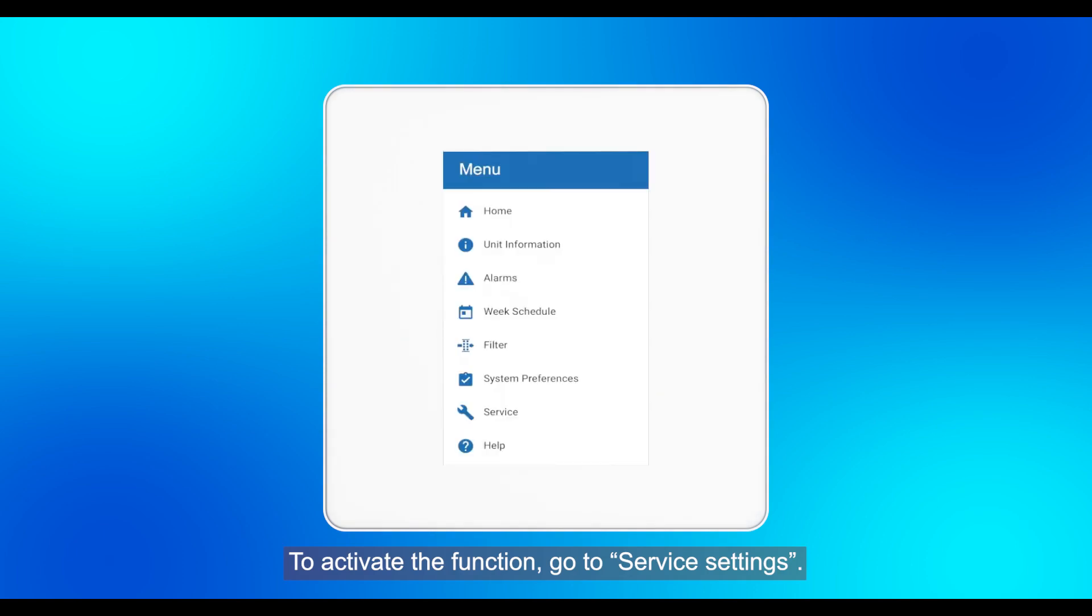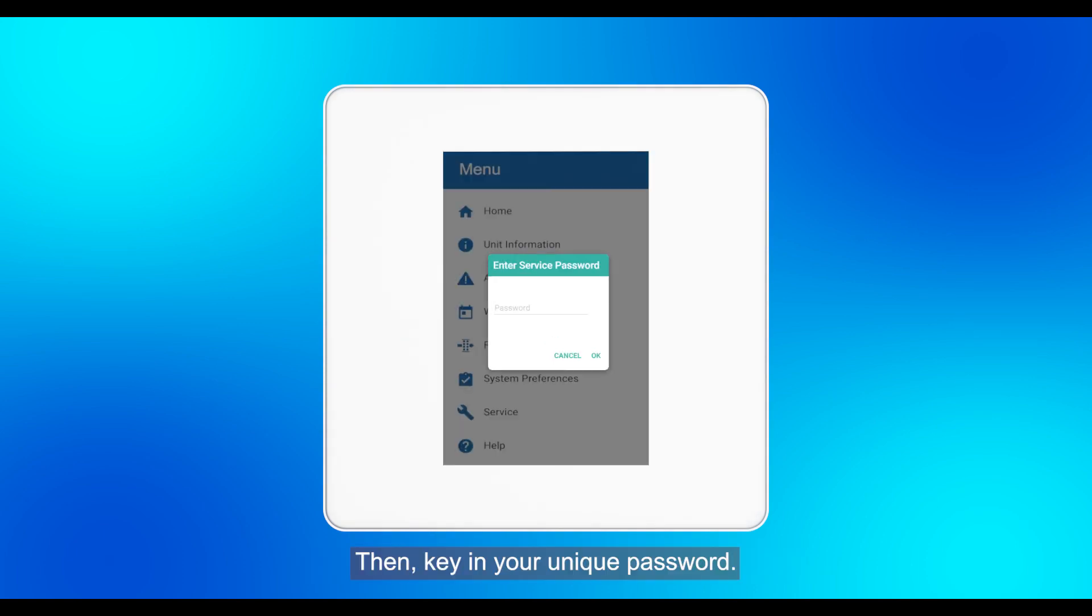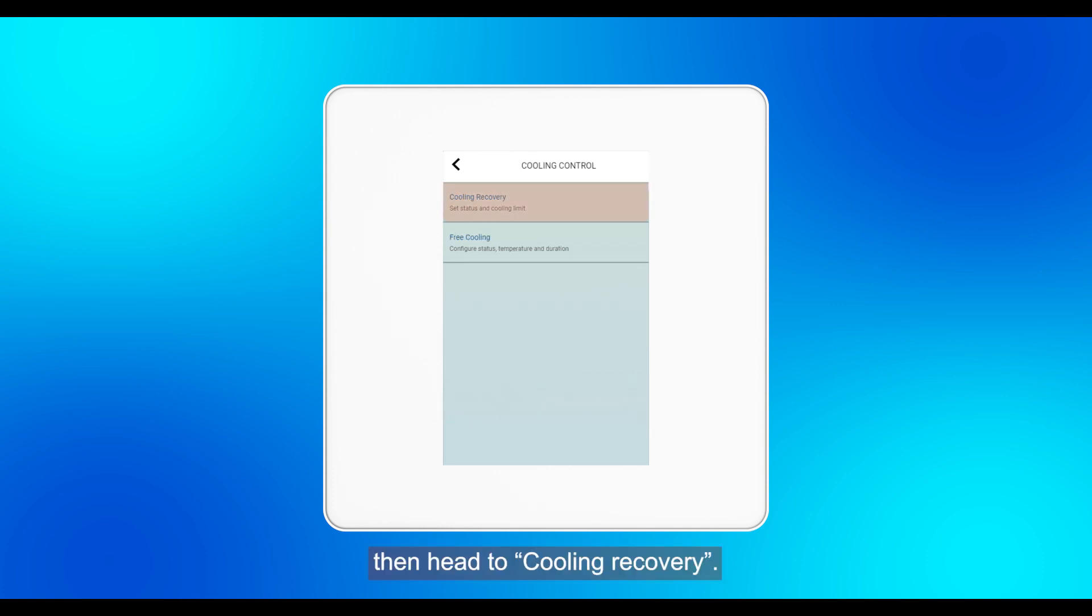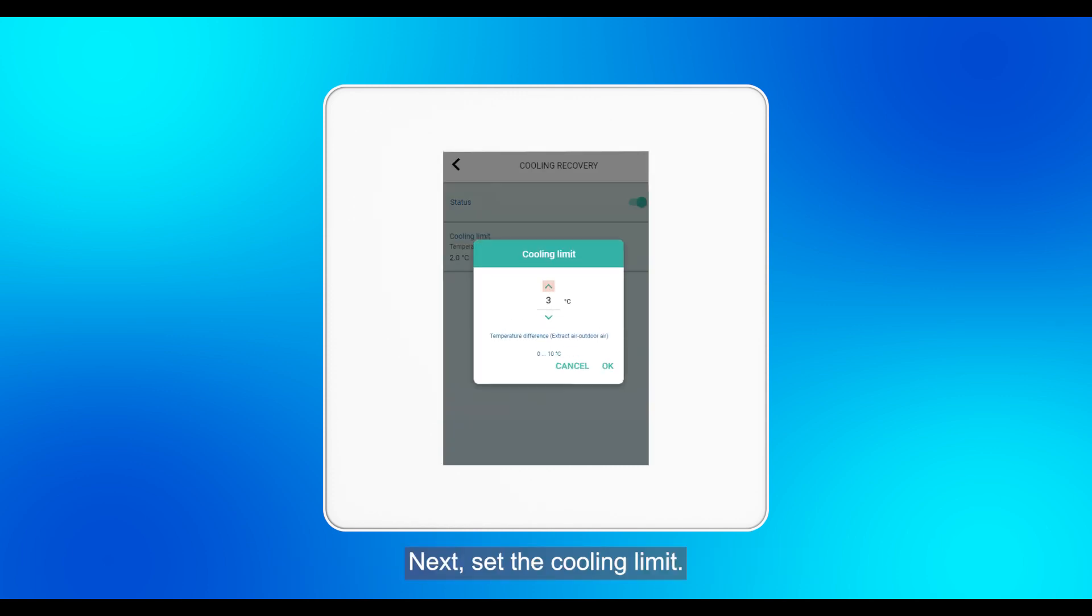To activate the function, go to service settings, then key in your unique password. Go to control regulation and select cooling control, then head to cooling recovery. Ensure that the status of the function is turned on. Next, set the cooling limit.